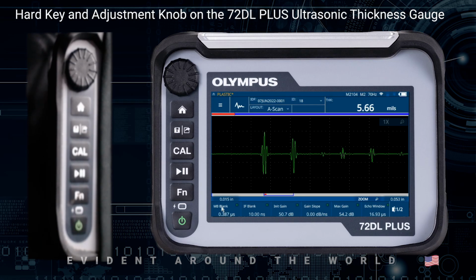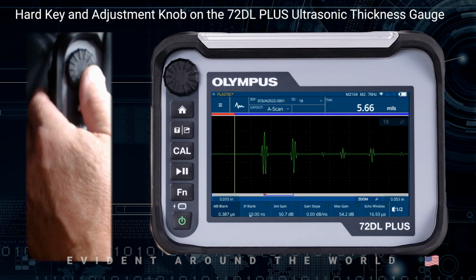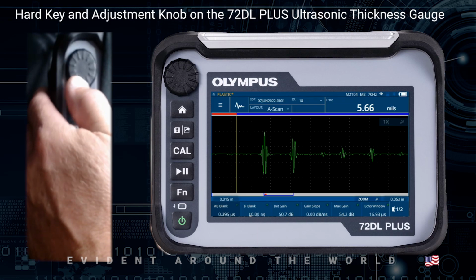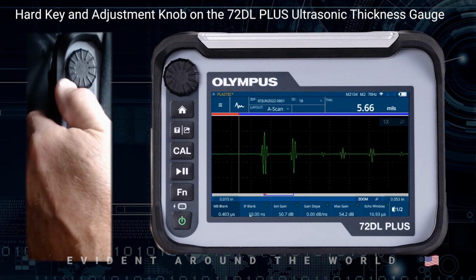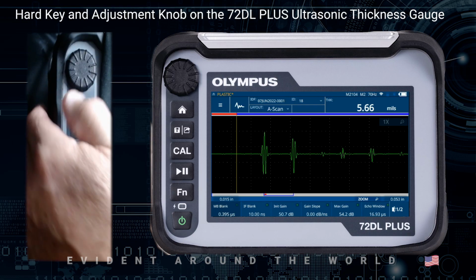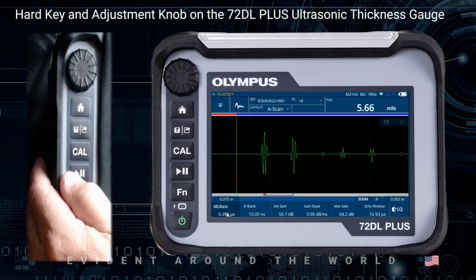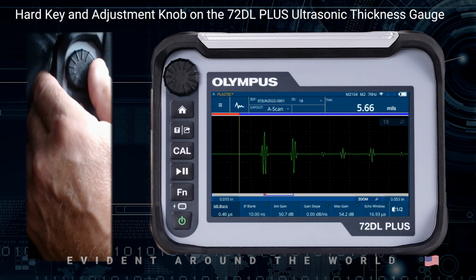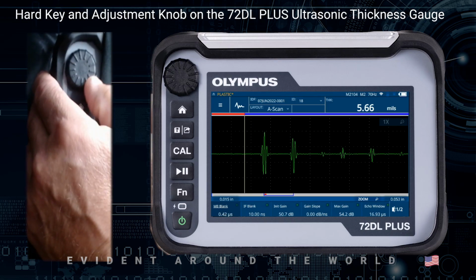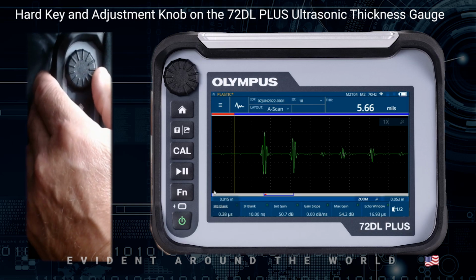So if I'm adjusting a parameter, for instance, in this case the main bang blank, I can simply touch on it and then use the knob adjustment to adjust its value, decreasing or increasing it. If I double click on it, the parameter will become underlined. When it's underlined, I can now do a coarse adjustment. That means that the adjustment will be a lot faster. So I can go back and forth between fine adjustment and coarse adjustment by simply clicking on it multiple times.